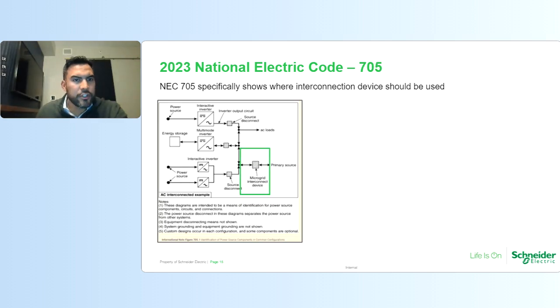And lastly here, I want to highlight this diagram that's in the National Electric Code. And if you could see there, I don't want it to be an eyesore, but highlighted there in green is the microgrid interconnection device. And if you look to the right, you have the primary source, which in this case could be a utility. And then to the left, you have your inverter-based resources. It could be a photovoltaic system, some type of carport or rooftop solar system.